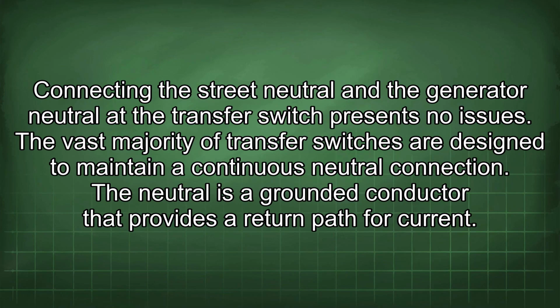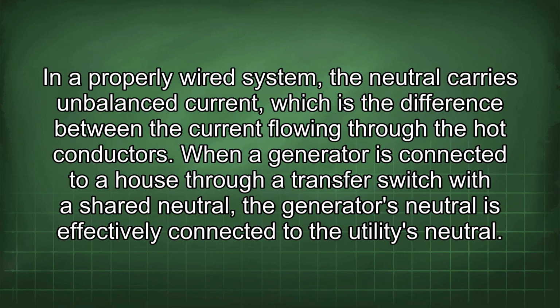Connecting the street neutral and the generator neutral at the transfer switch presents no issues. The vast majority of transfer switches are designed to maintain a continuous neutral connection. The neutral is a grounded conductor that provides a return path for current. In a properly wired system, the neutral carries unbalanced current, which is the difference between the current flowing through the hot conductors. When a generator is connected to a house through a transfer switch with a shared neutral, the generator's neutral is effectively connected to the utility's neutral.